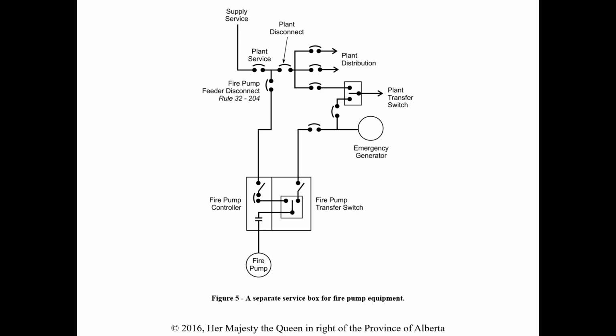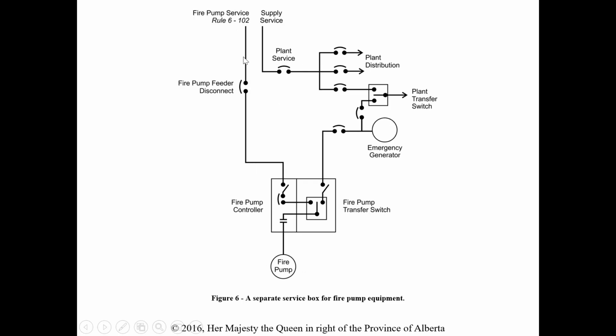Then it talks about fire pumps specifically, again, because there's code rules for it. So it talks about that you can have a service box for a fire pump that is a separate service box from the equipment, or we can actually have one that's a separate supply. Okay, so we have, here's our service or supply coming down in here, and we have a separate disconnect going to our fire pump. Here's our transfer switch that would transfer over from the supply to the emergency generator and to make sure this fire pump works still. And then we have one that's just a total separate service that it talks about here too. Okay, so those are the two different scenarios that they're going to talk about.